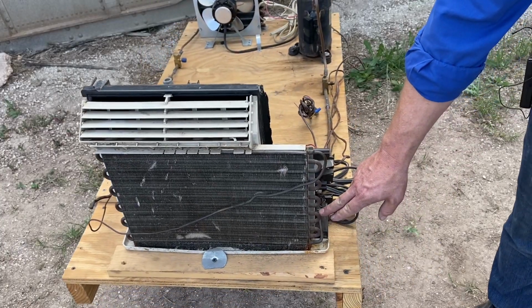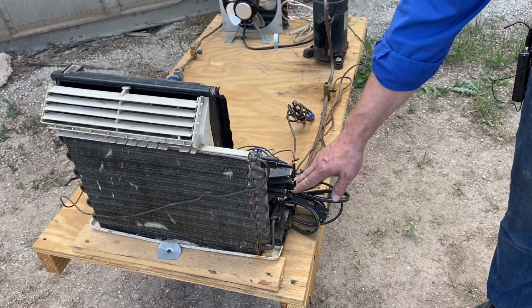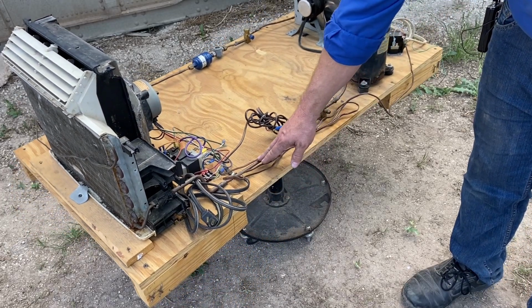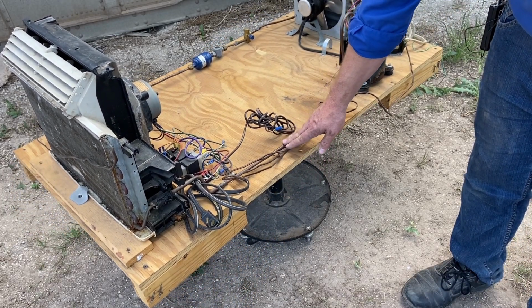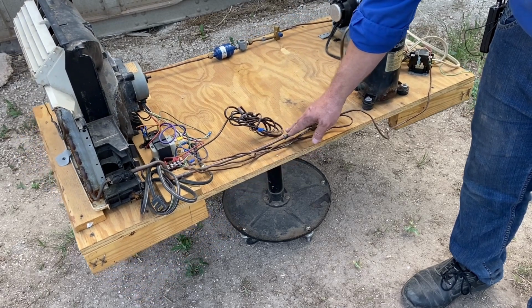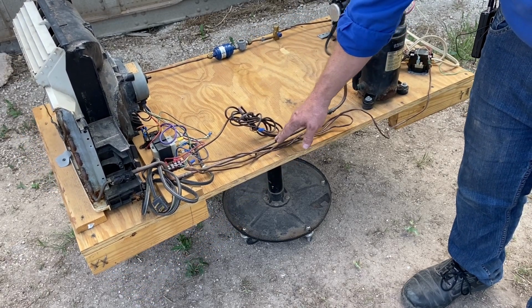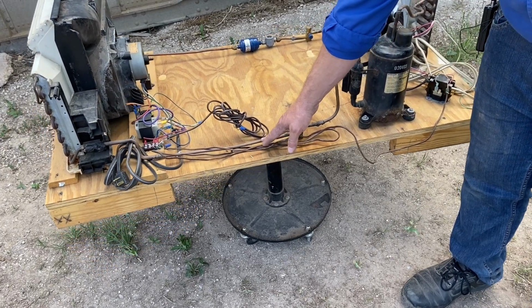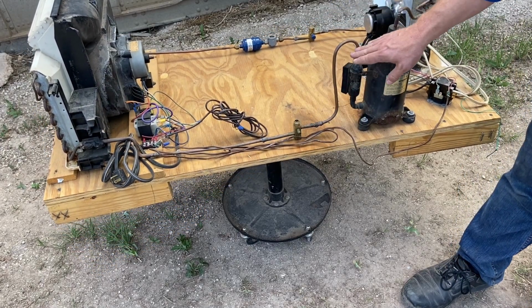So this line is our suction line, also known as our gas line. If we touch this line, it's going to be cool to the touch. This line is going to be a low temperature, low pressure, superheated vapor. According to you and your feelings, it's going to be low temperature. According to the refrigerant in science, it's superheated. It is a vapor form. So that vapor is going to go all the way back to the compressor.